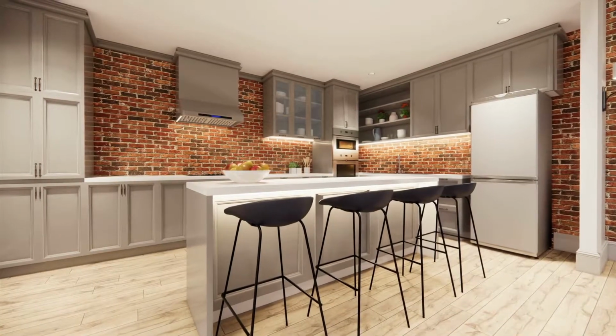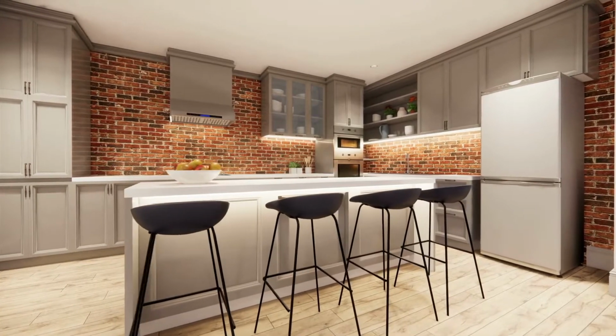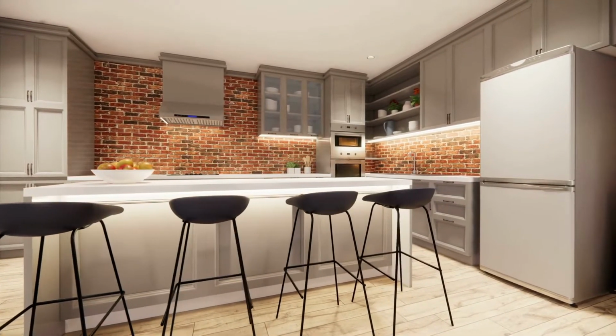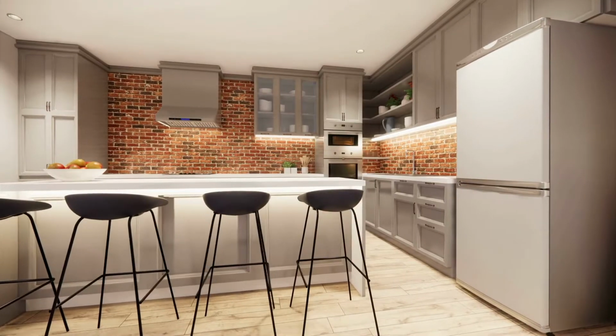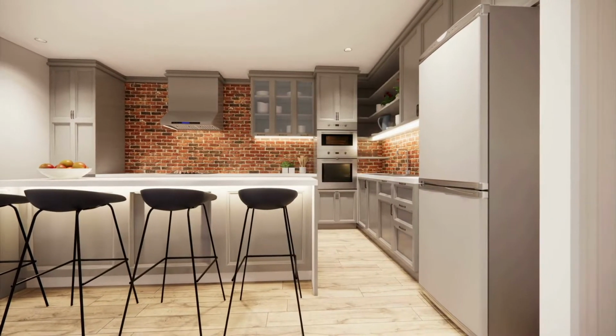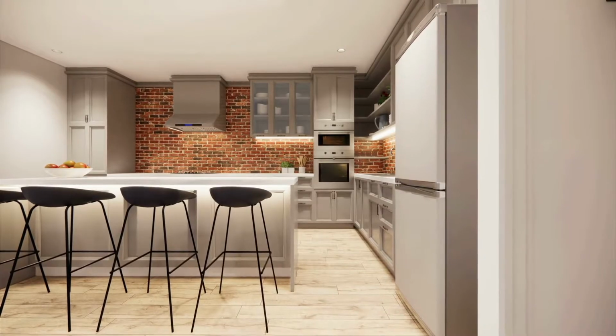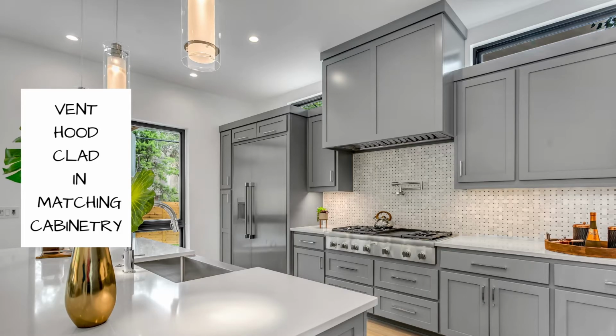Sometimes there is confusion of how close a hood top can be to the surface of your range. For a non-combustible range top, the vertical clearance above the range cooktop surface to the bottom of any approved vent hood or other approved non-combustible material should be no less than 24 inches. The vertical clearance above the range surface to the bottom of any combustible material, such as wood or metal cabinets, should be no less than 30.